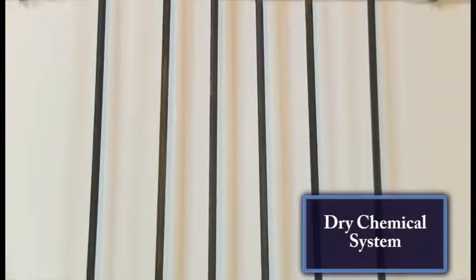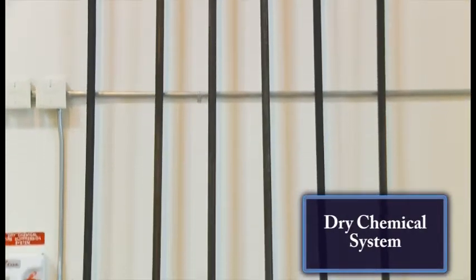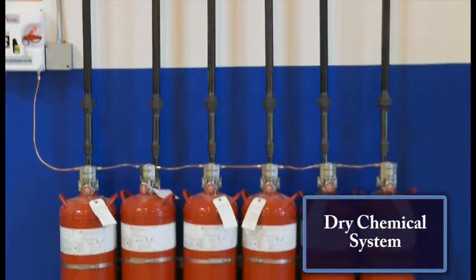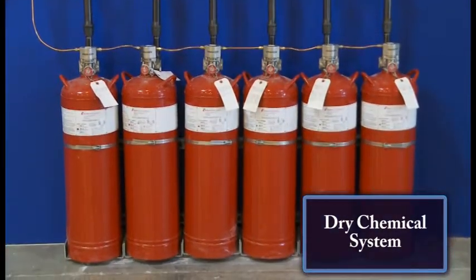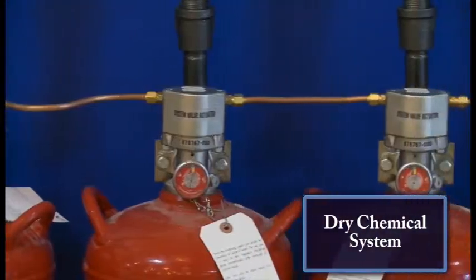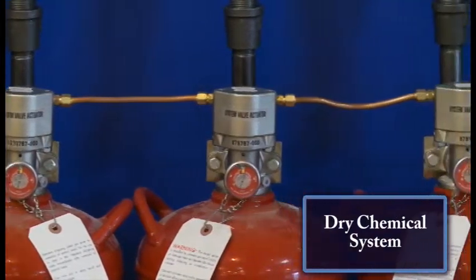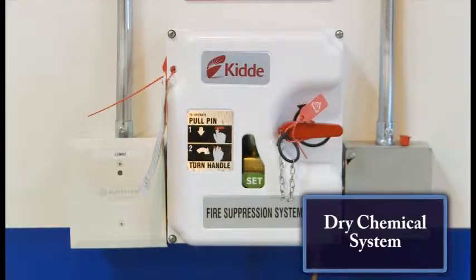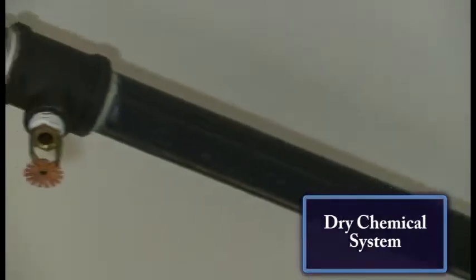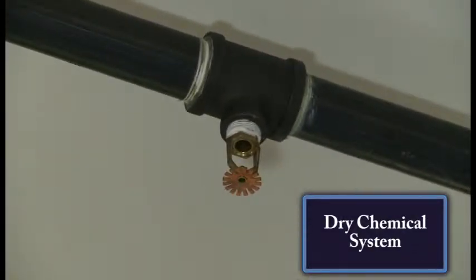The Kidde Dry Chemical System is a fixed dry chemical system consisting of a supply of dry chemical stored in a multiple cylinder and valve assembly. Each cylinder is pressure activated by a system valve actuator. The system can be actuated either automatically and/or manually using mechanical, electrical, or pressure actuation devices. Upon actuation, the dry chemical is discharged through agent distribution piping and specially designed nozzles positioned throughout the protected area.